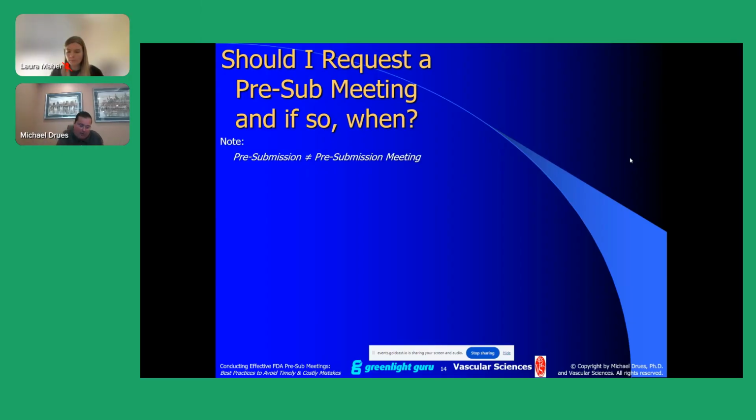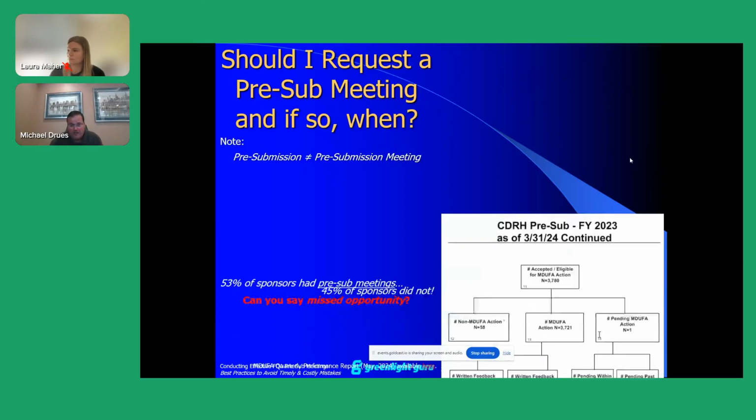That means preparing the submission, which we'll talk about in a few minutes. That means getting FDA's feedback. That means having a pre-sub meeting if you choose to have a meeting. And then that means following up by submitting your meeting notes and so on after the fact. So all of that is part of the pre-submission process. The pre-submission meeting is only that portion of the process that involves the meeting. So the pre-submission process is much broader than just the meeting itself.